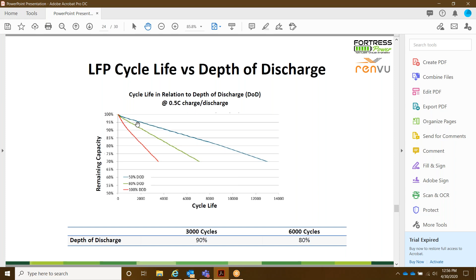So a lot of the different parameter setting guides for the different batteries we have with those different inverters can be found at fortresspower.com/resources. But a thing I did want to bring up here is that we recommend 80% DoD for 6,000 cycles, 90% DoD for 3,000 cycles. Max charge current, 100 amps for the eVault, 90%, 170 amps. So with more depth of discharge, you will be able to put out more amps. More information on parameters and with the different inverters can be found on our website, like I said below.